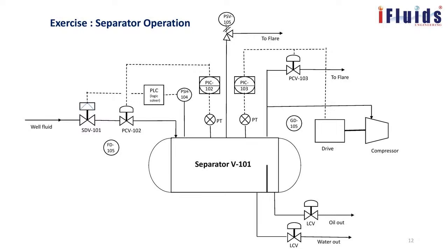The next question is how SOP is considered as one of the barriers. SOP represents human intervention — if pressure is going high and the inlet control valve PIC-102 is not responding, the SOP provides standard instructions for what to do in case of instrument malfunction. The operator can directly take control of the control valve from the control room, monitoring pressure and adjusting the valve to maintain safe pressure. That is how SOP is considered a barrier against high pressure.